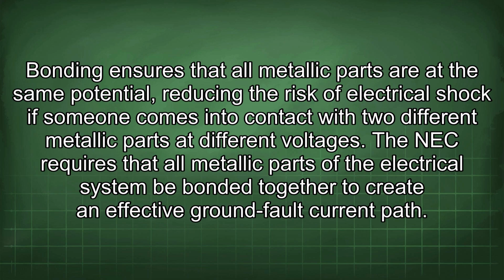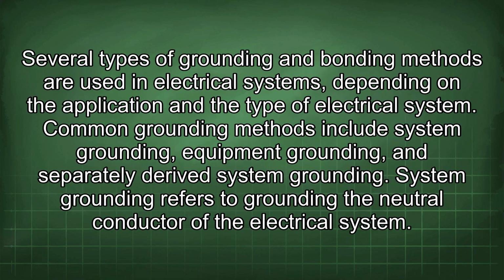The NEC requires that all metallic parts of the electrical system be bonded together to create an effective ground fault current path. Several types of grounding and bonding methods are used in electrical systems, depending on the application and the type of electrical system. Common grounding methods include system grounding, equipment grounding, and separately derived system grounding.